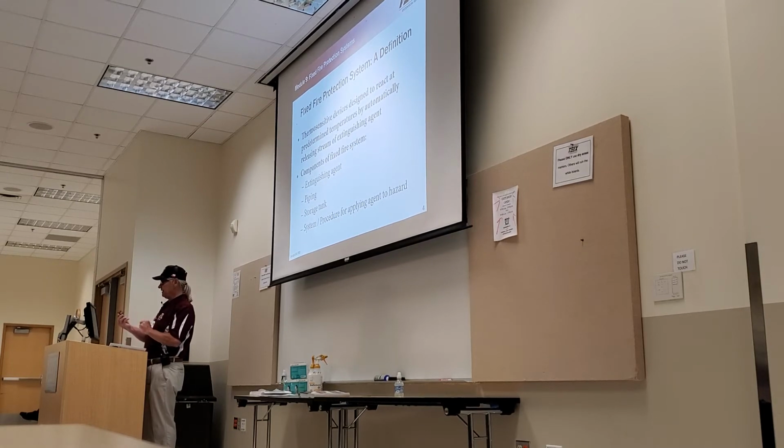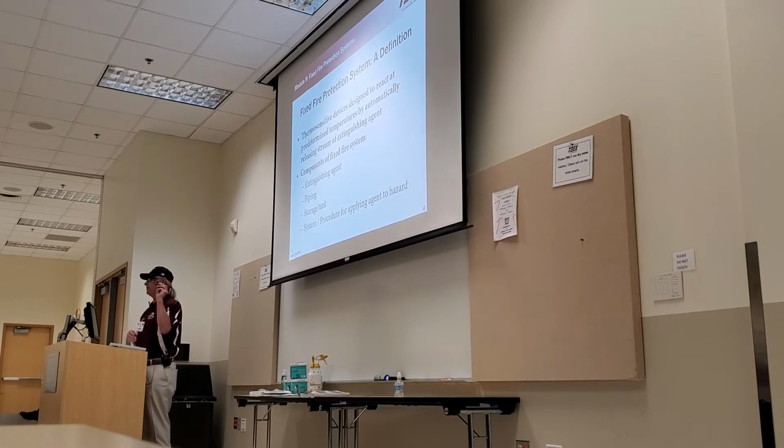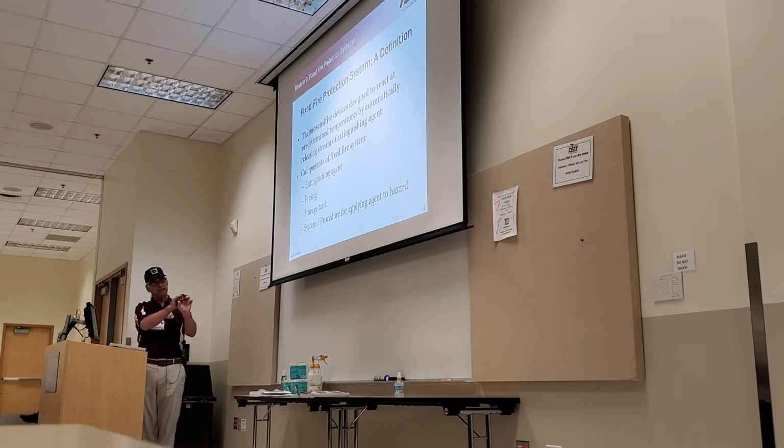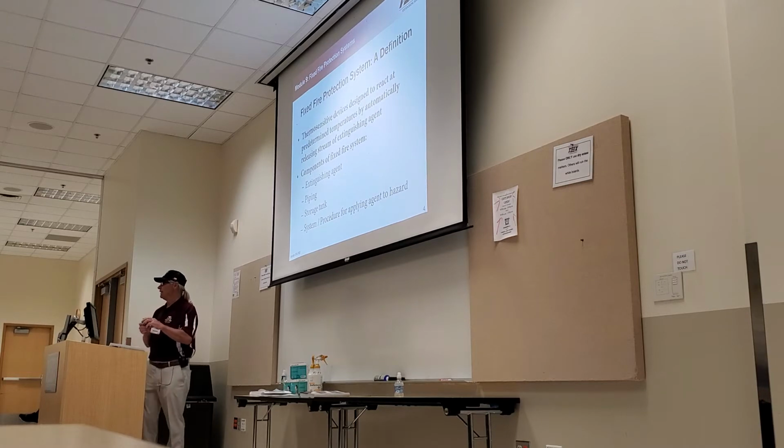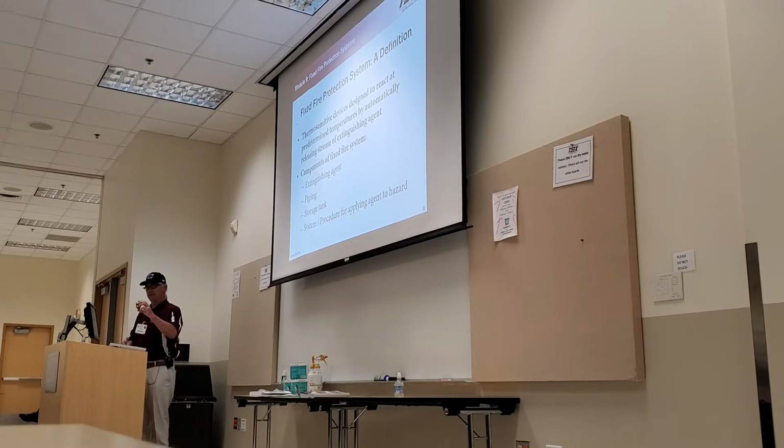And this one's a 1974. UL says you can use this for 50 years, and if you want to keep it, you take 10% of the sprinkler heads and send them to be retested. If they pass, then you don't have to put in new heads, but it's probably cheaper to put new heads in there. So it's basically a two-piece link with solder. This 165 is about 5 degrees either way, so it's 160 to 170. And when that pops, it just lets water out of that head.